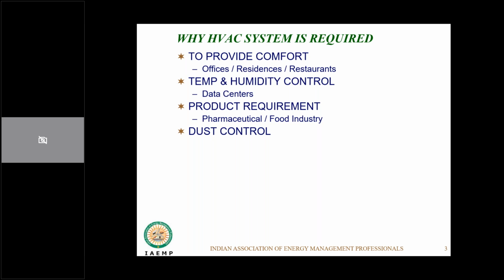Dust control, I talked a bit about pharma, and electronics is also subject to this. In fact, electronics industry design, semiconductor industry design, is much more stringent on dust control than the pharmaceutical perspective. Normally in pharma, the normal clean room classification is class 100. When I say class 100, it is basically 100 particles of 0.3 micron and above in a volume of, say, 1 cubic foot. When we do the electronics or semiconductor industry, we recently did one lab where it had to be within 10. So the requirement was much more stringent.